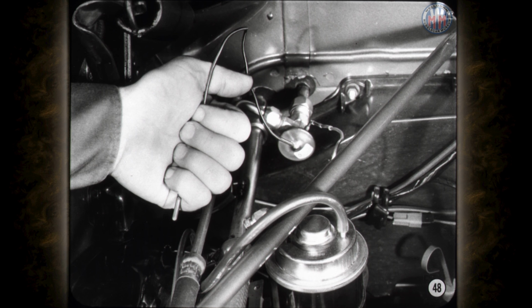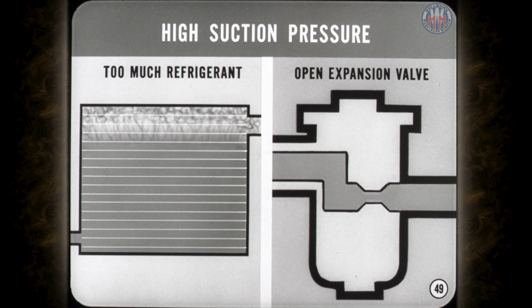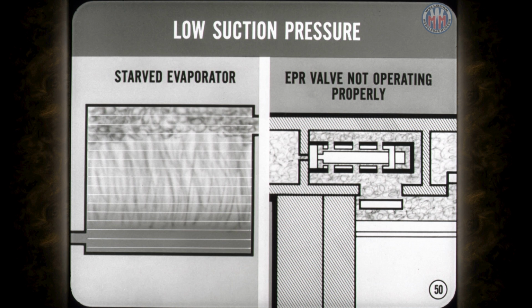Now, what's the story if evaporator suction pressure is higher or lower than normal? Well, high suction pressure alone can be caused by too much refrigerant or an open expansion valve. But when both of the side gauges read high and remain high as you speed up the engine, the compressor capacity may be low. Now, in the opposite direction, low suction pressure can be caused by a starved evaporator or an EPR valve not operating properly.